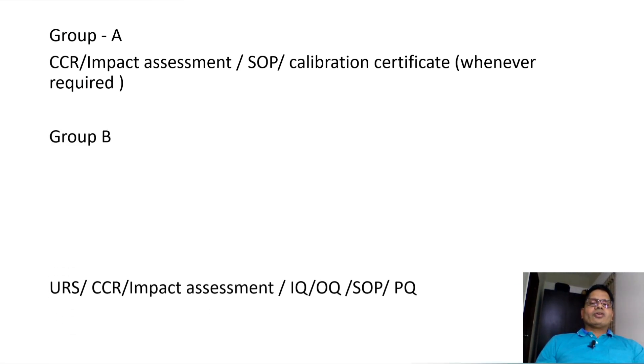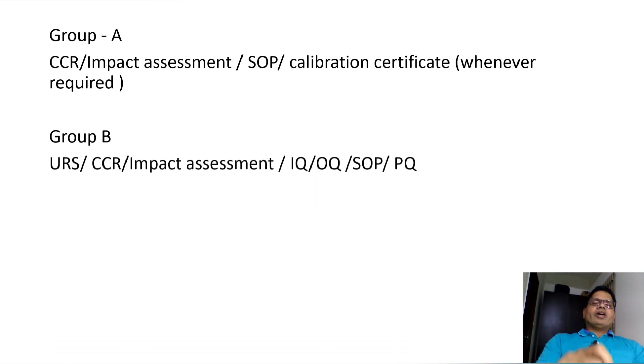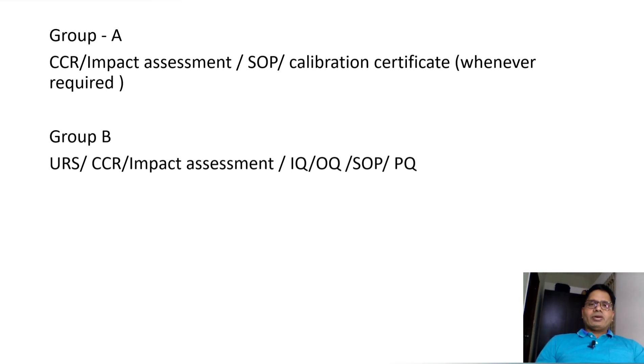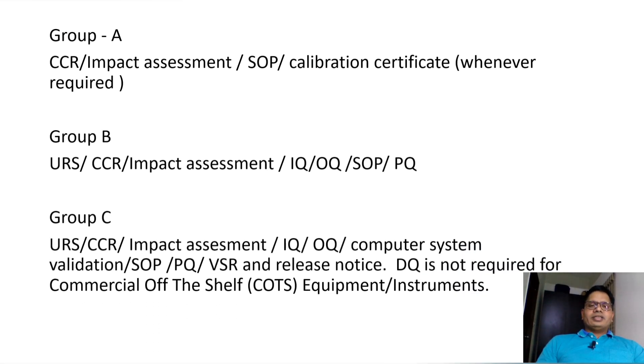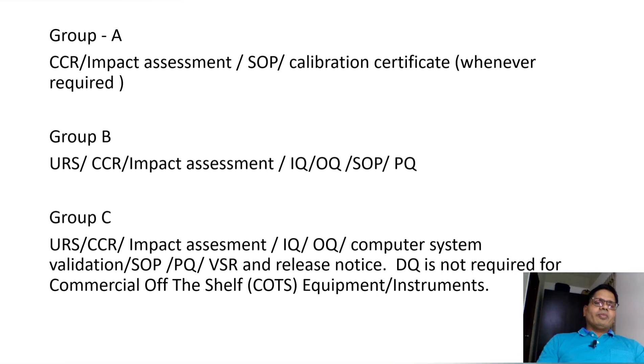For Group B instruments, the required documents are: user requirement specification, change control, impact assessment, installation qualification, operational qualification, SOP, and performance qualification. For Group C instruments, the requirements are: URS, change control, impact assessment, installation qualification, operational qualification, computer system validation, SOP, performance qualification, and a validation summary report with a release note.